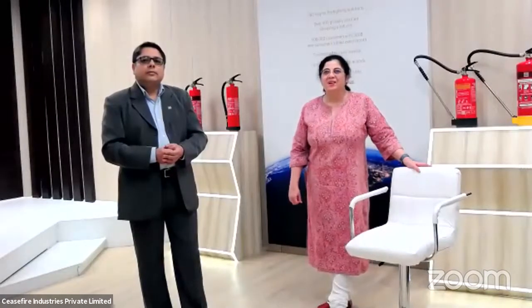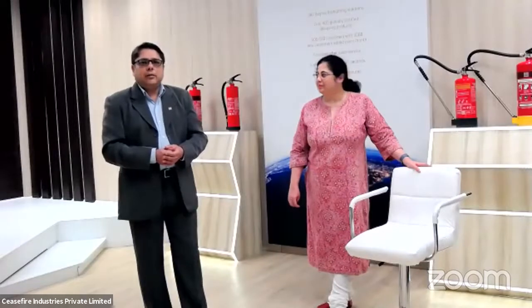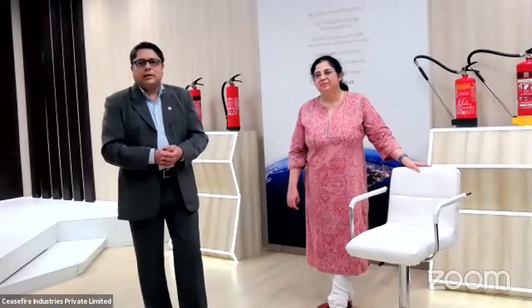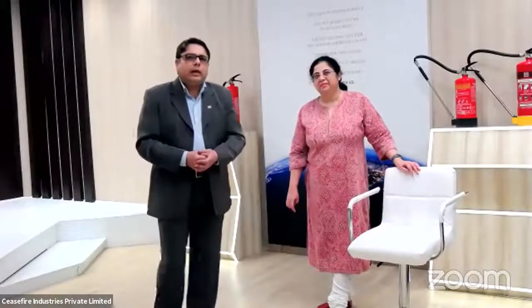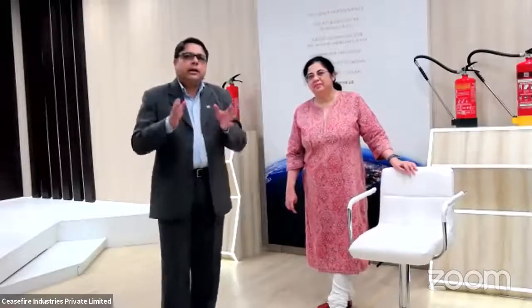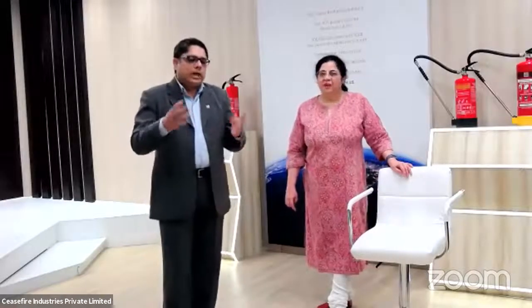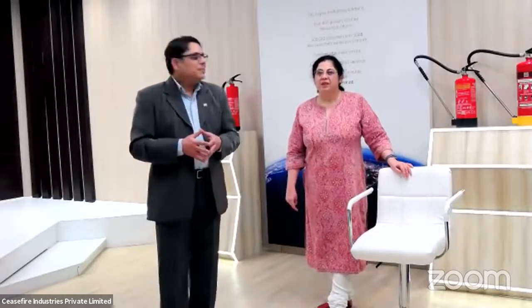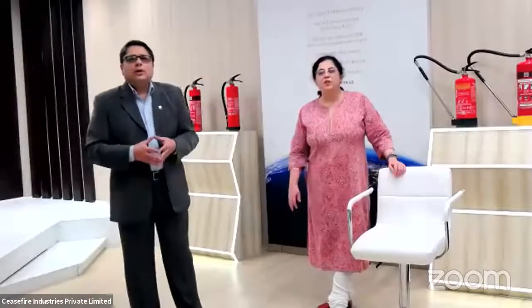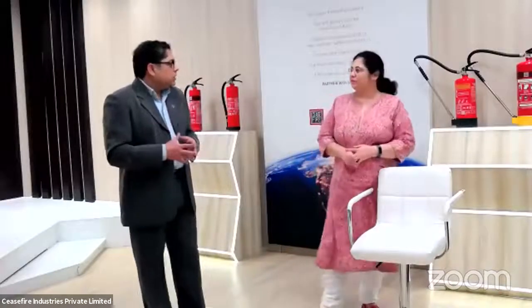So what is the agent's expiry time? If you're talking about gases, most of these have a limitless expiry time, but we are limited by the laws of the land which require that agent cylinders be checked with a hydrostatic pressure test every 3 years, or every 5 years depending on whether it is carbon dioxide or other gases or products. So it could either be at the end of 3 years, or for CO2 at the end of every 5th year, and for some further products we can go up to 6 years. But the agents have a very long life - it's only that they have to be replaced when we do the hydrostatic test and refill the cylinders. That is the time we need to change them.